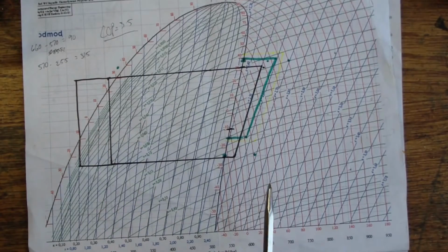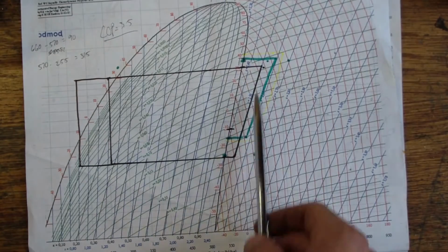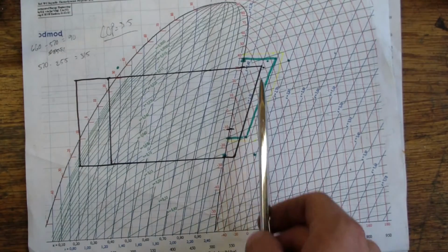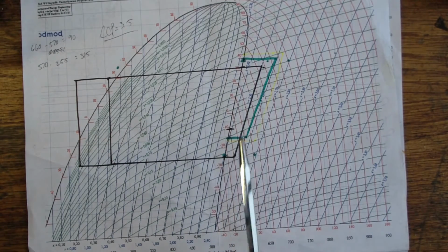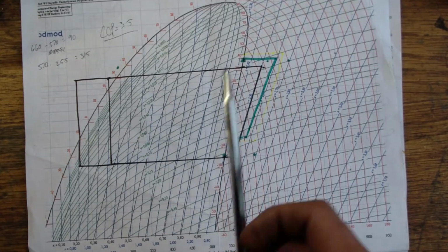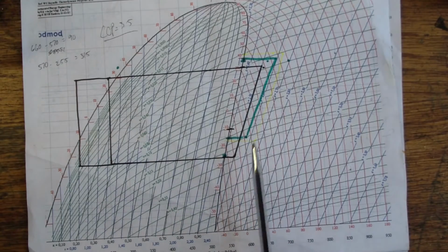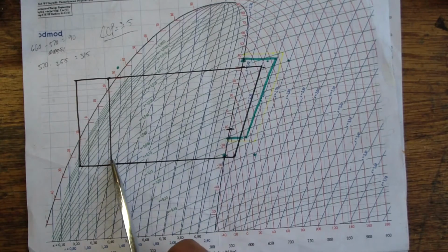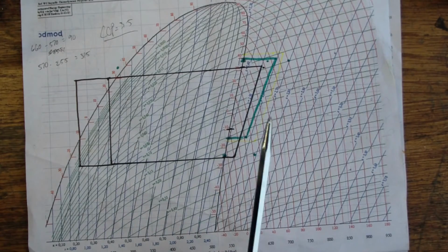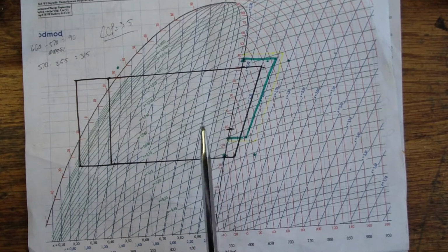If you know the efficiency, I suppose you could use this change in enthalpy and compare that to your compressor amp draw or the wattage consumed, to determine how many pounds per minute or per hour are flowing around. But let's not get into that too deeply right now. From a theoretical standpoint, if we divide the change in enthalpy from compression into the change in enthalpy from the evaporation portion of the cycle, we should be able to determine what our actual COP is.